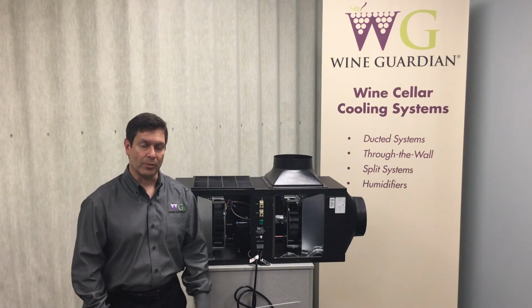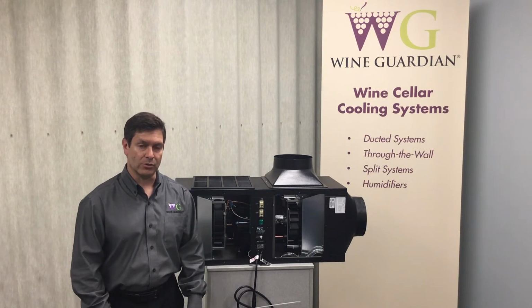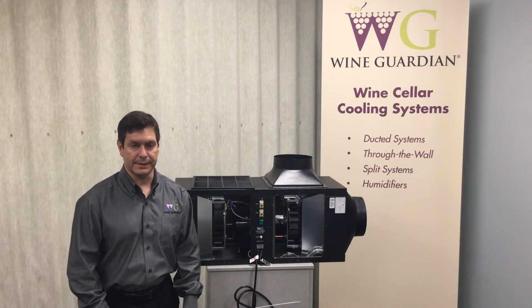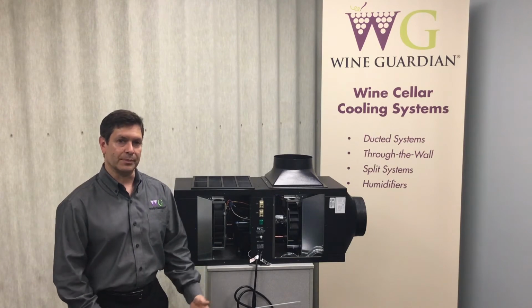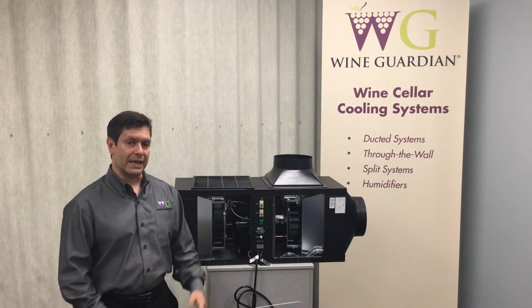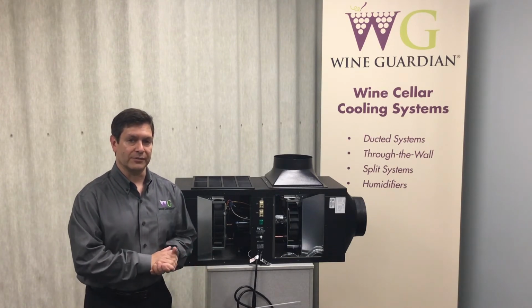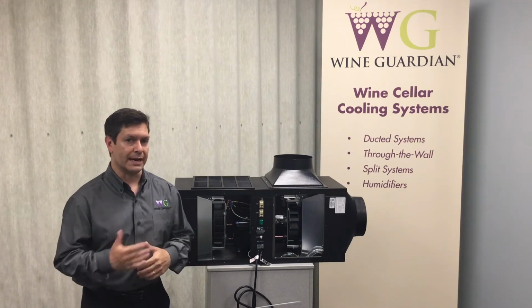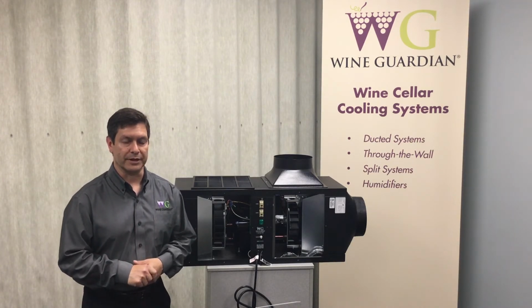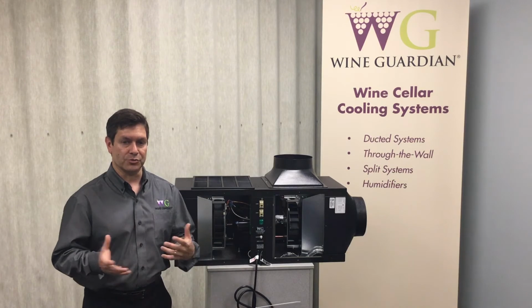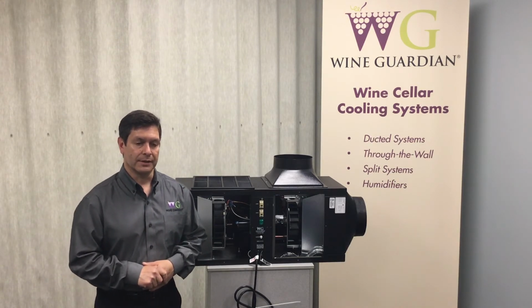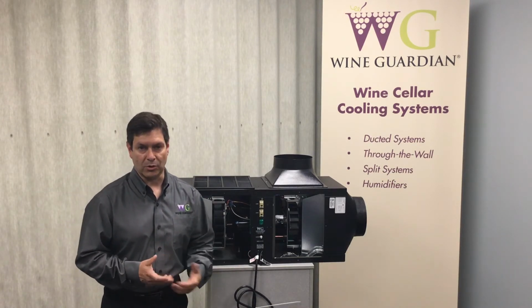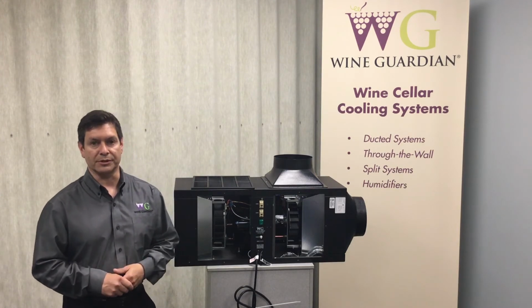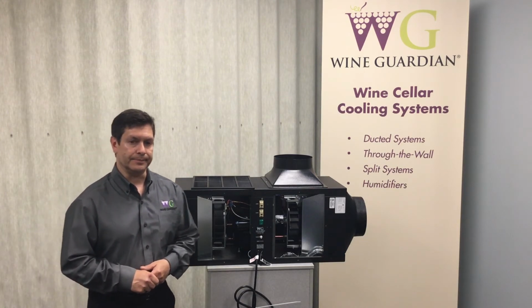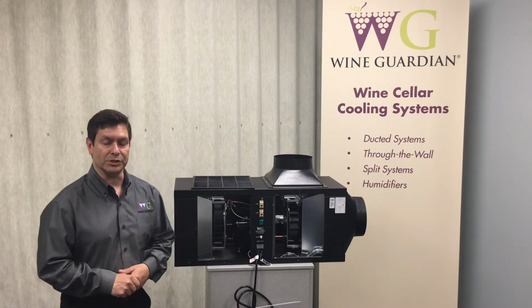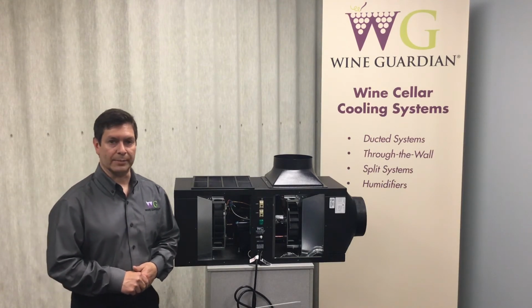They have the same performance characteristics as the air-cooled as far as capacities, and the water temperature range should be anywhere from a low of 45 degrees Fahrenheit up to a high of 85 degrees Fahrenheit. And the water usage really depends on the size of the unit. Like I said, they can be applied to our 025 all the way up to our 200 series, and they work very well with geothermal or cooling tower applications.